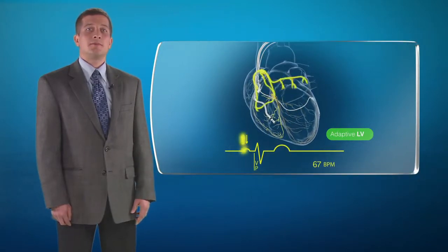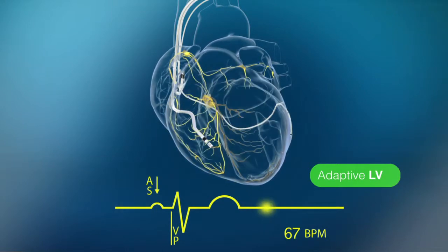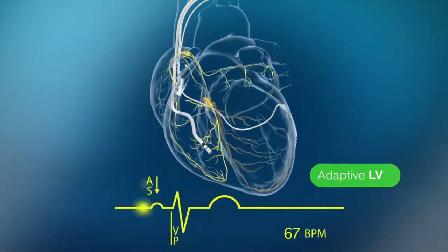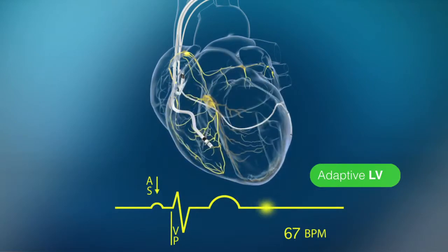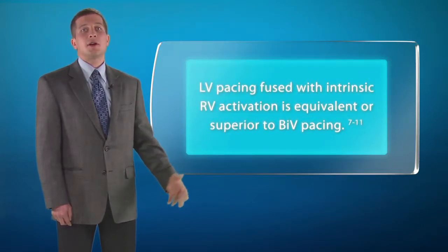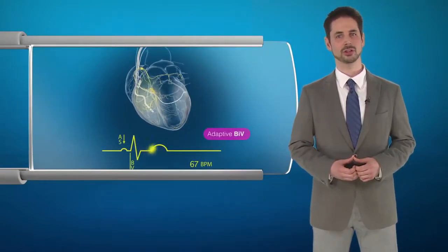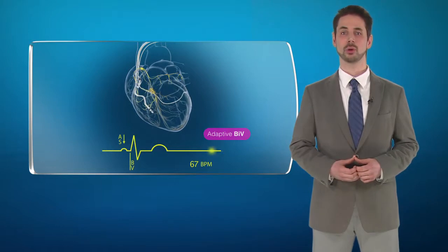Previous clinical research has helped us to determine optimal CRT parameters. For example, if the patient's intrinsic rhythm and atrioventricular conduction are normal but there is left bundle branch block, left ventricular pacing with appropriate timing is more favorable than biventricular pacing. The goal is to achieve fusion between paced and intrinsic conduction so that contractions are resynchronized. However, if atrioventricular conduction is prolonged, or arrhythmia or elevated heart rate is present, the preferred pacing configuration is biventricular pacing, which works to restore both interventricular and atrioventricular synchrony.